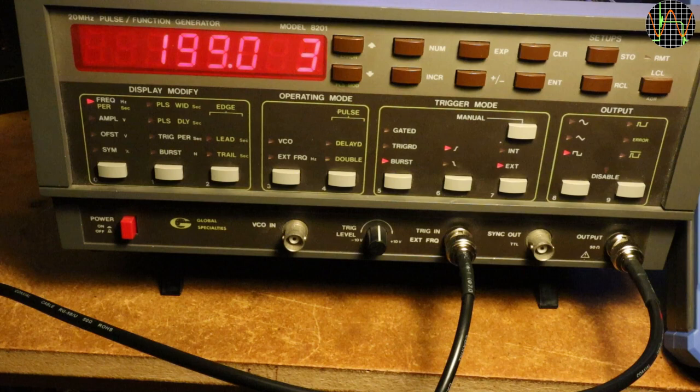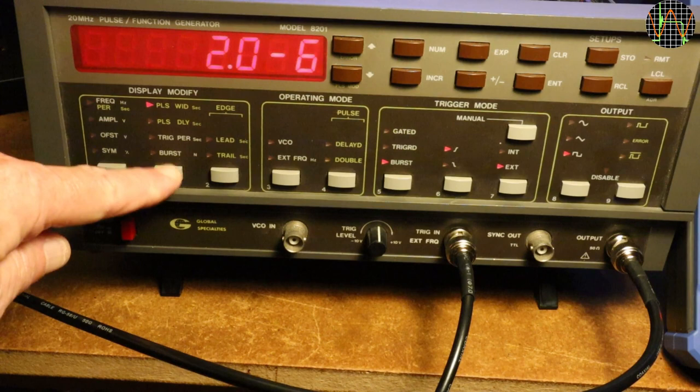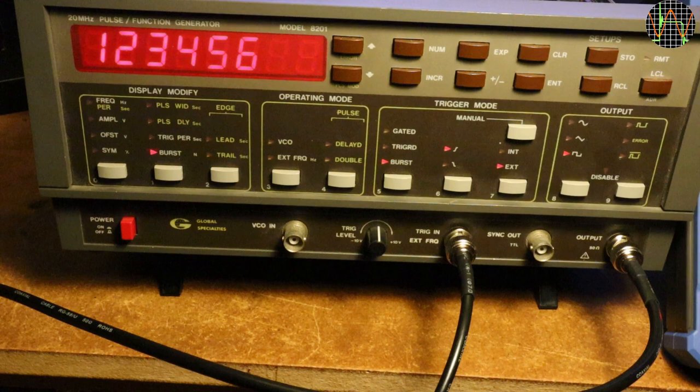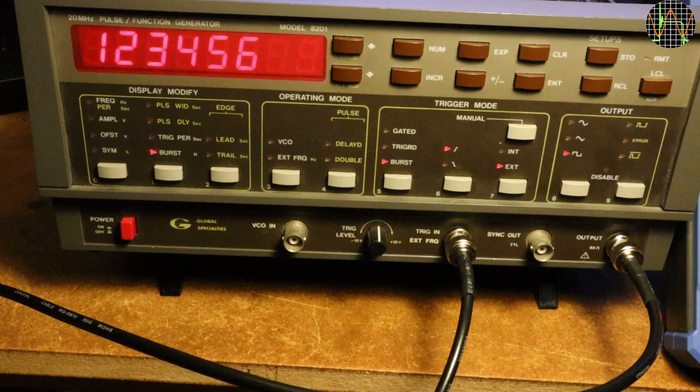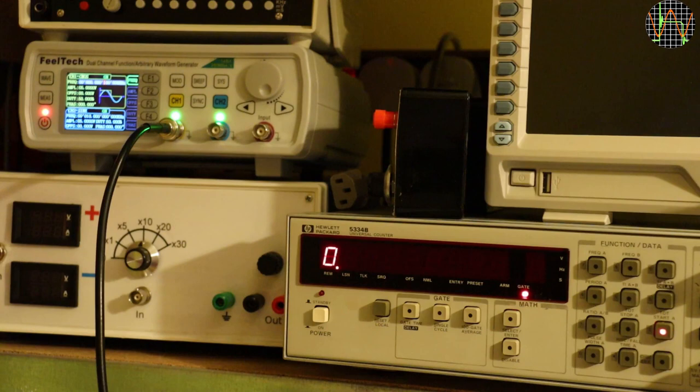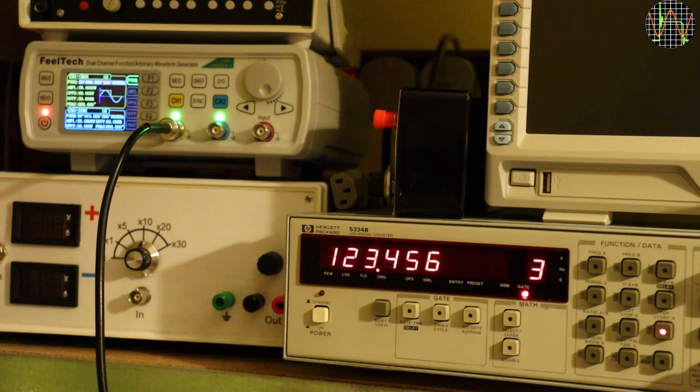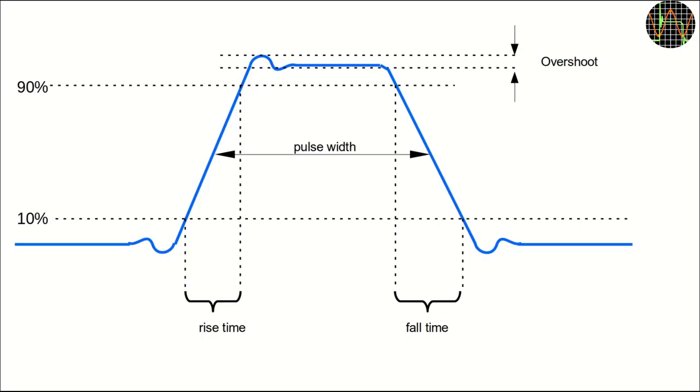Here as part of the performance test, the generator is running at 199kHz. The burst count is set to 123456 and the waveform is rectangular. I set my other function generator providing the external trigger signal to 0.1Hz that is a trigger every 10 seconds. This gives me enough time to manually reset the totalizer on my frequency counter. 123456 as specified, so the burst mode works fine.